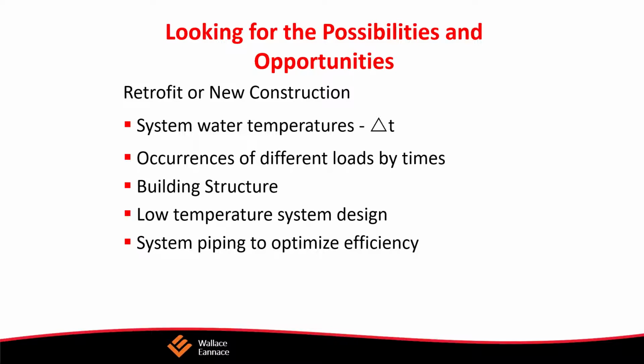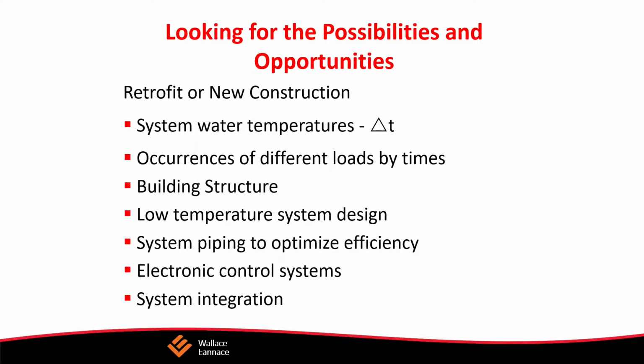One of the things we want to do is lower the temperature of the water in the system, because then we have an advantage of being able to produce a more efficient heating system. So we're always looking to lower the temperature of the system design. We look to optimize the system by using system piping alternatives to improve efficiency. We can use electronic control systems to improve system efficiency, and also to integrate the systems together so they work uniformly, and you don't have one section pulling against another. You have each section operating in unison to get the system to work at maximal efficiency.